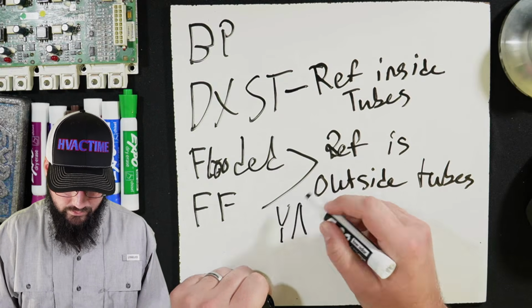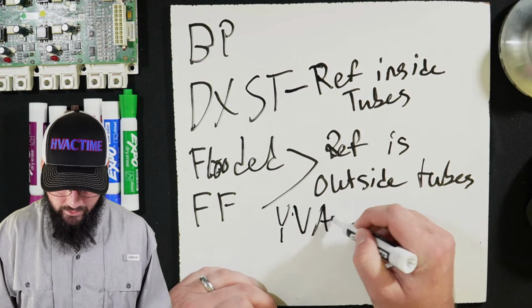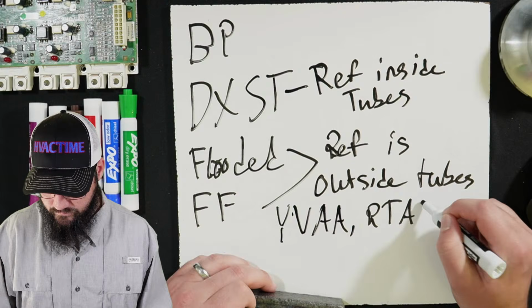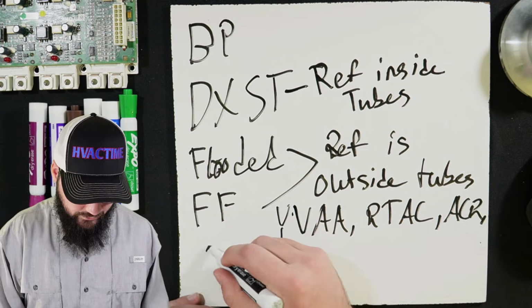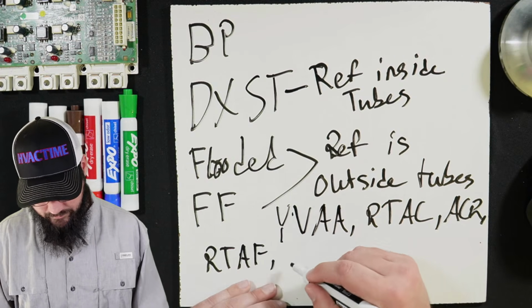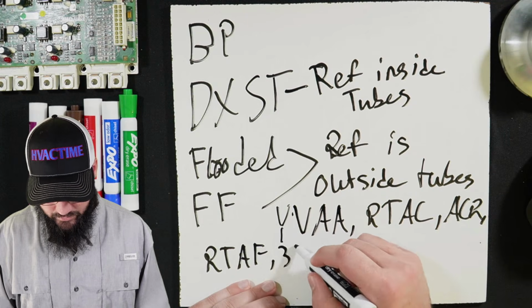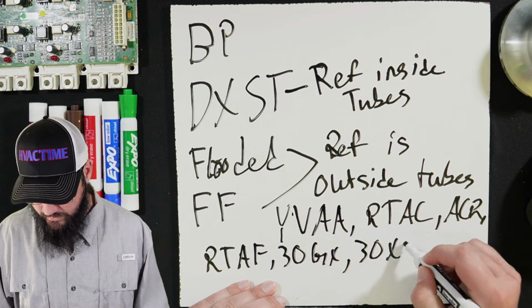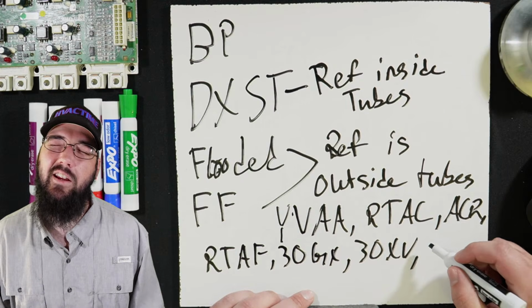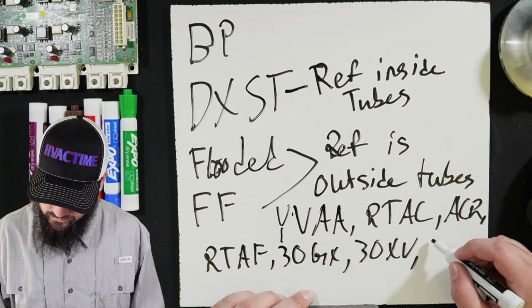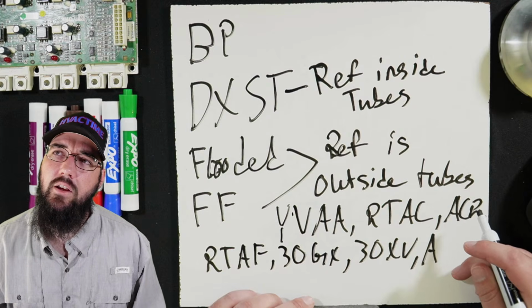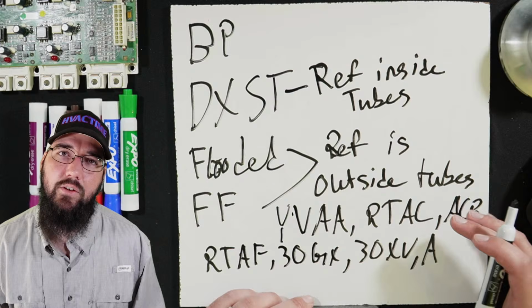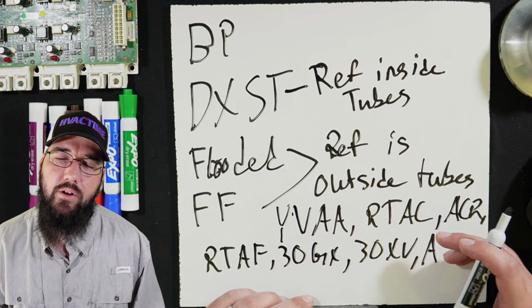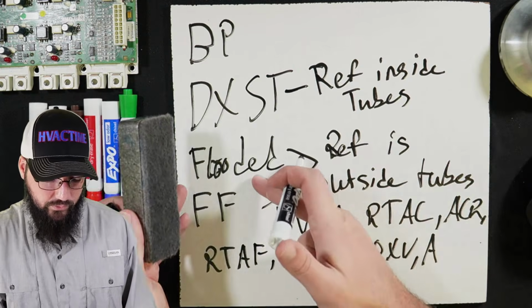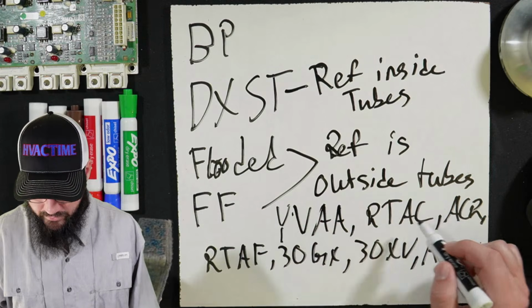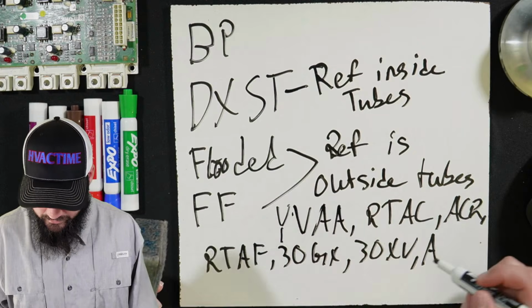So we could go with a YVAA, okay? A RTAC, a ACR, RTAF, the 30GX, 30XV by Carrier. The was it AWS, AGZ, the AGZ. I'm blanking on the Daikin ones now. Anyway, Daikin has a couple of flooded. Pretty sure they have a couple of flooded air cooled. Anyway, these are some examples that would use either flooded or falling film. So technically, YVAA, falling film, RTAC, falling film. 30GX is a flooded. 30XV is a flooded.